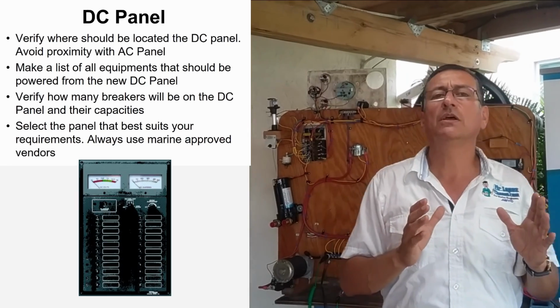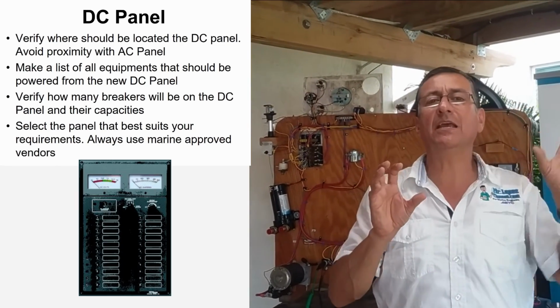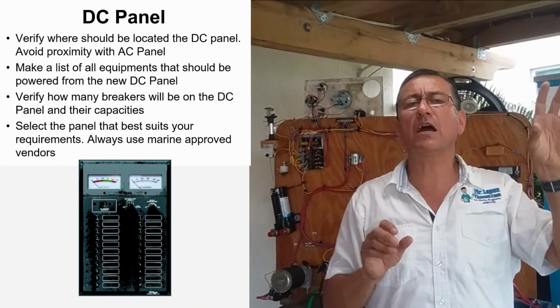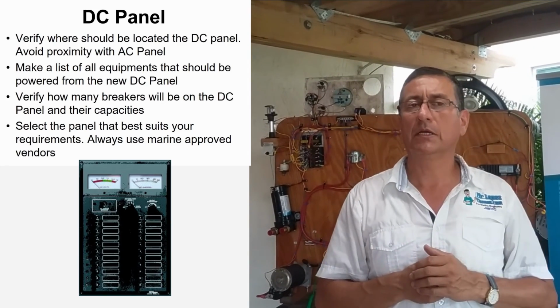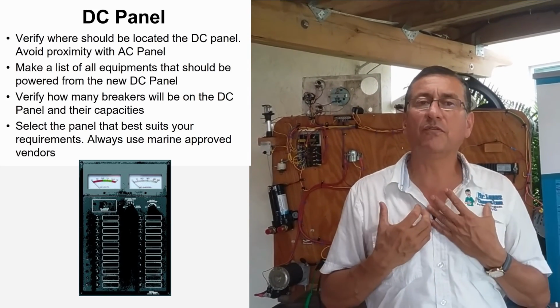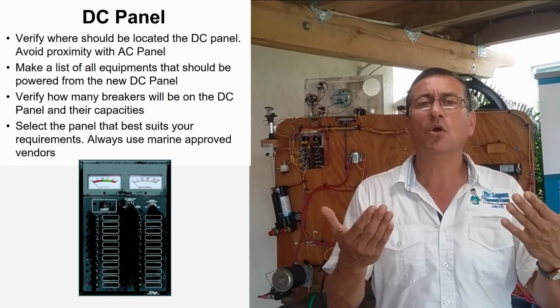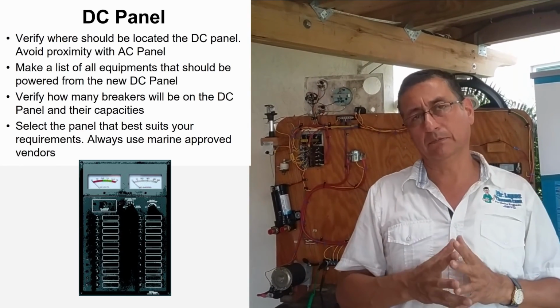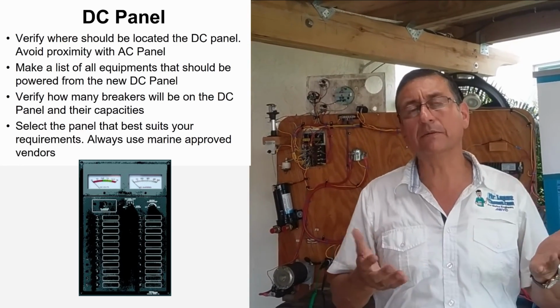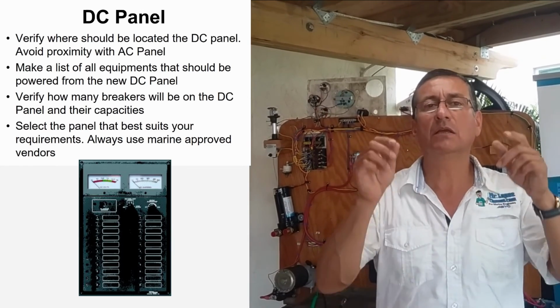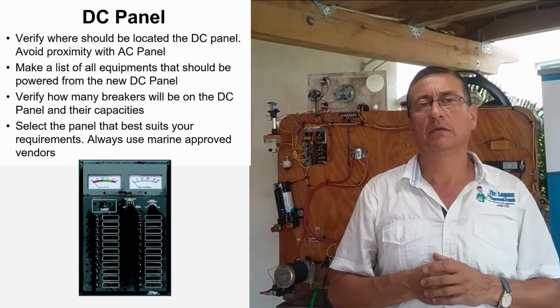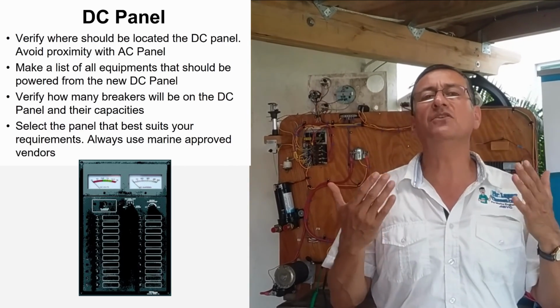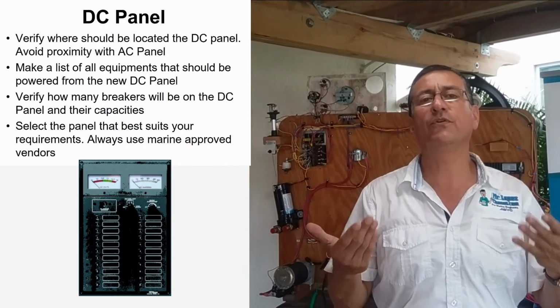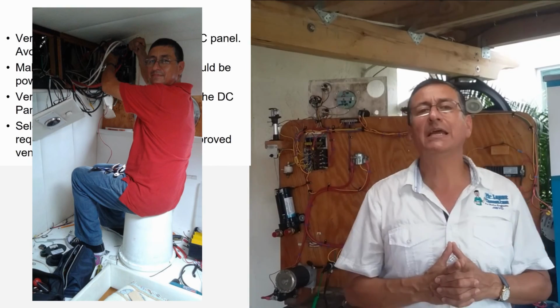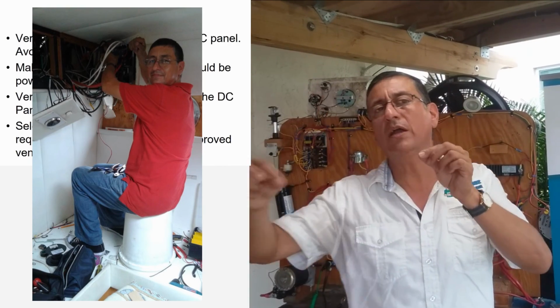Or there are panels where you need to install the gauges for voltmeter, ammeter, and battery bank tester separately. I prefer, if possible, to select a new panel with those gauges incorporated. It's better, easier to do the wiring, easier for installation and troubleshooting future problems, and you avoid extra long wires between the gauge and the breakers.